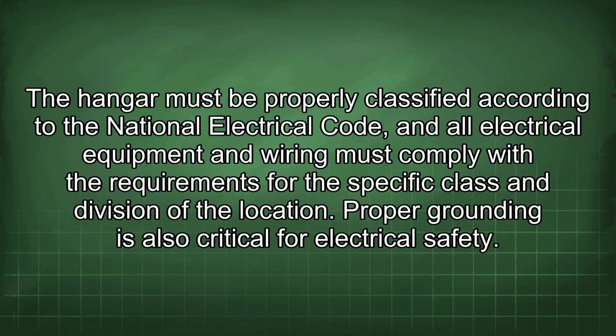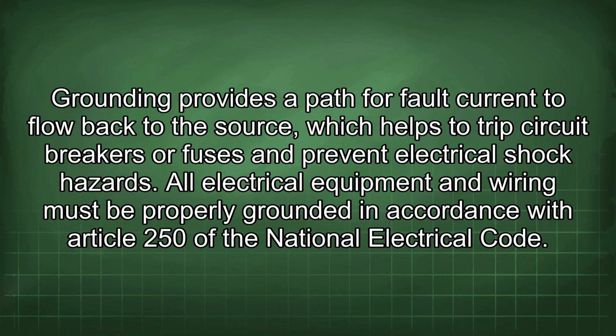Proper grounding is also critical for electrical safety. Grounding provides a path for fault current to flow back to the source, which helps to trip circuit breakers or fuses and prevent electrical shock hazards. All electrical equipment and wiring must be properly grounded in accordance with Article 250 of the National Electrical Code.